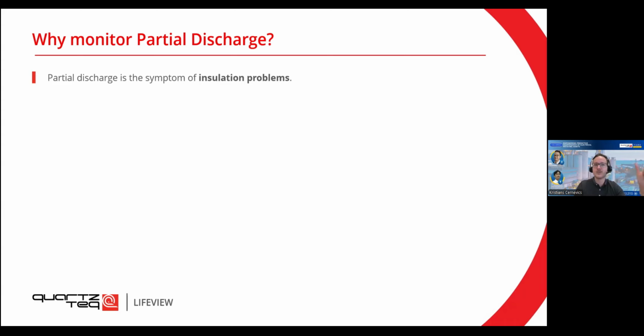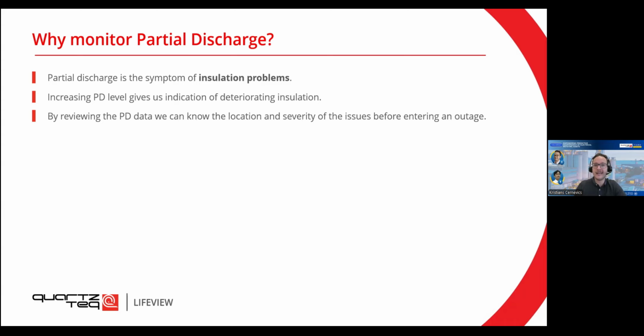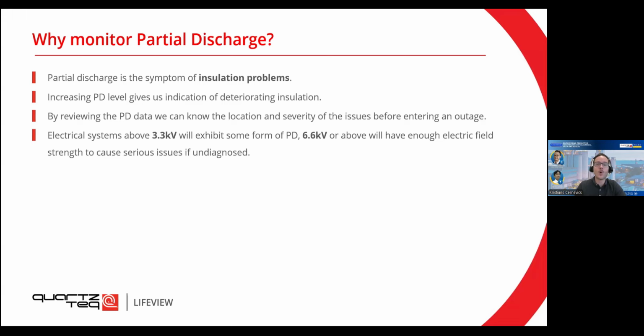So partial discharge is a symptom of insulation problems, small gaps, small shifts, where there is air between the two conductors and discharges happen there. Increasing PDs give us an indication of how bad the insulation is. And by reviewing the data, we can also try to pinpoint what kind of discharge it is and where the location of this is, before we need to enter an outage. And as I mentioned before, all electrical systems above around 3.3 kilovolts will exhibit some form of PD. For machines of 6.6 kilovolts and higher, you would have enough electric field strength to actually cause serious issues.